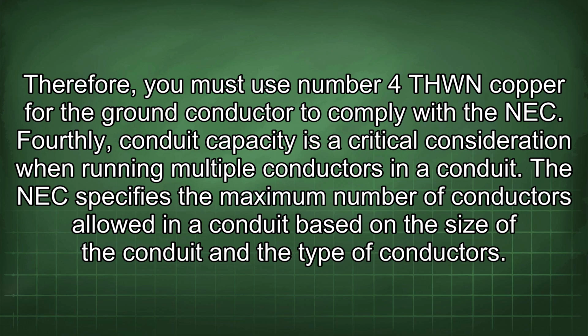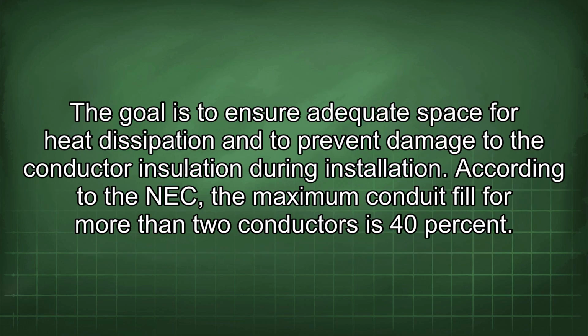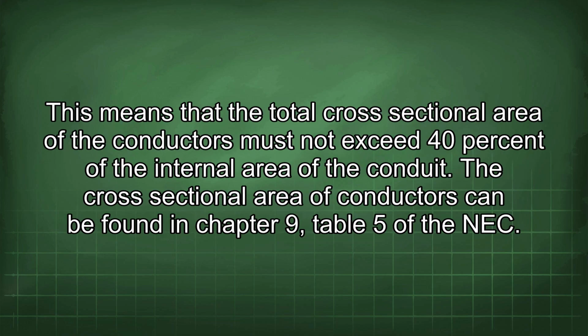Fourthly, conduit capacity is a critical consideration when running multiple conductors in a conduit. The NEC specifies the maximum number of conductors allowed in a conduit based on the size of the conduit and the type of conductors. The goal is to ensure adequate space for heat dissipation and to prevent damage to the conductor insulation during installation. According to the NEC, the maximum conduit fill for more than 2 conductors is 40%. This means that the total cross-sectional area of the conductors must not exceed 40% of the internal area of the conduit. The cross-sectional area of conductors can be found in Chapter 9, Table 5 of the NEC.